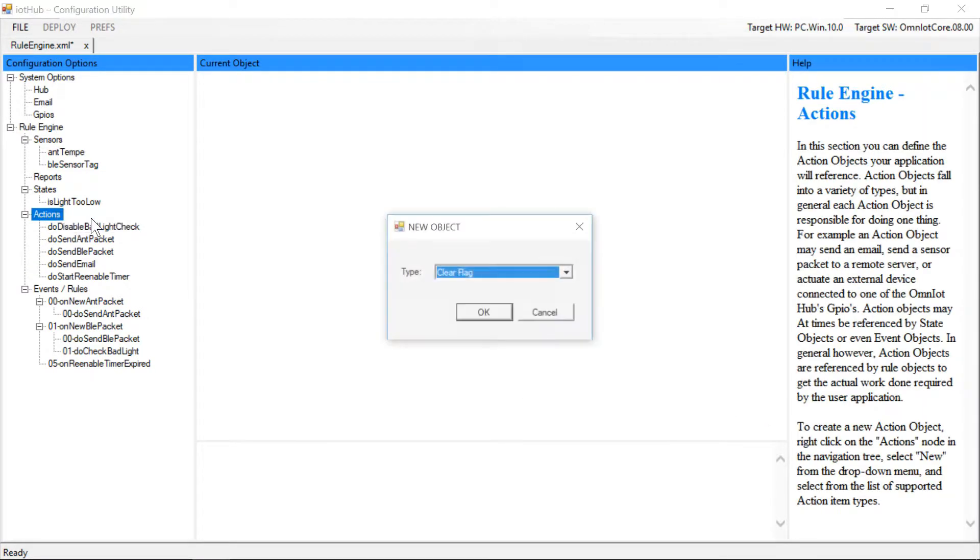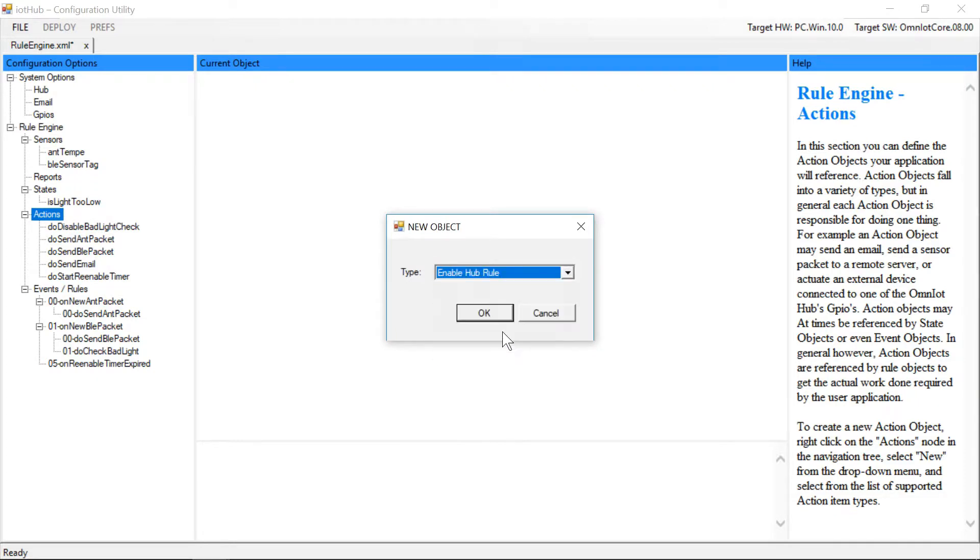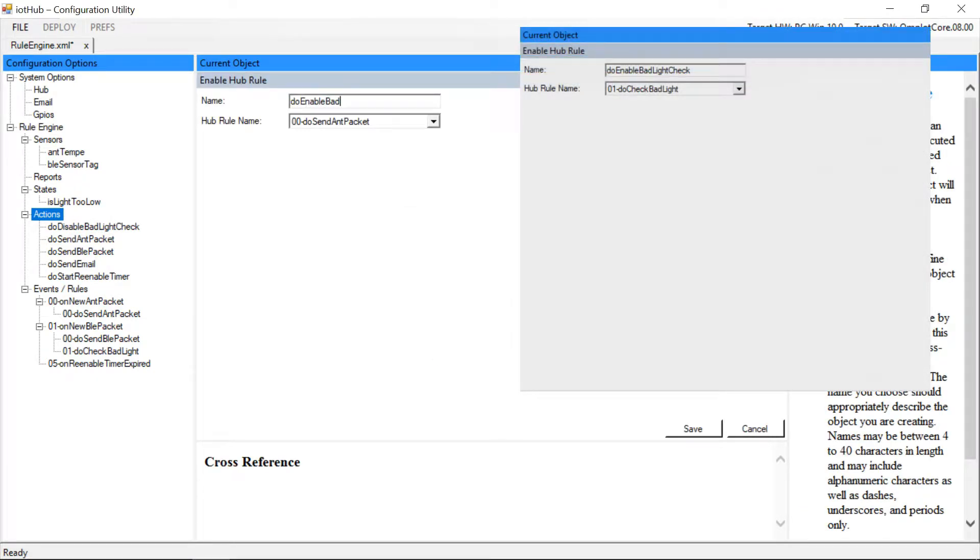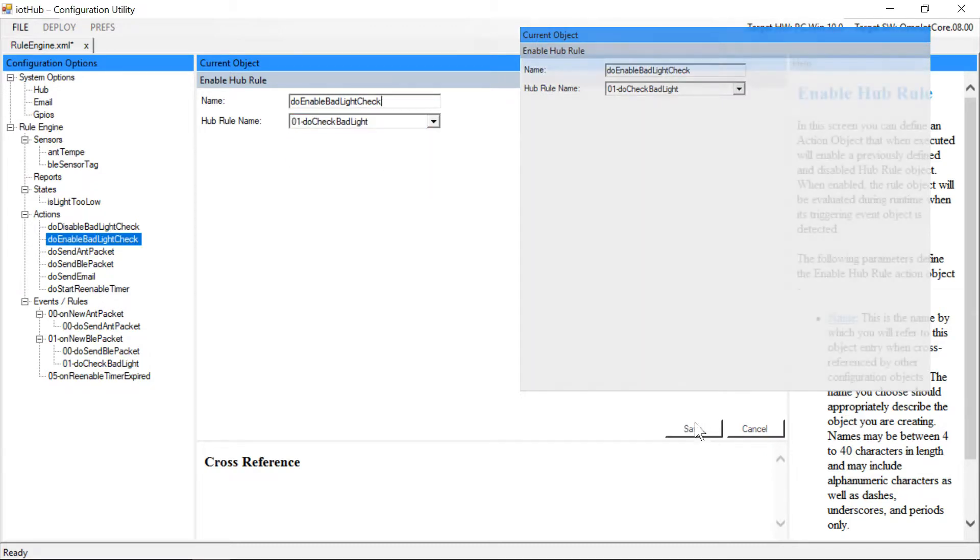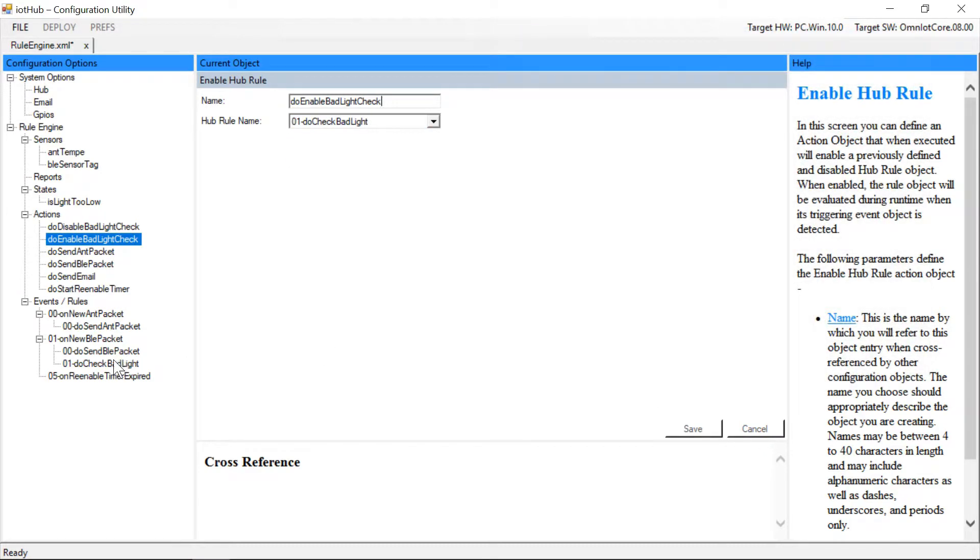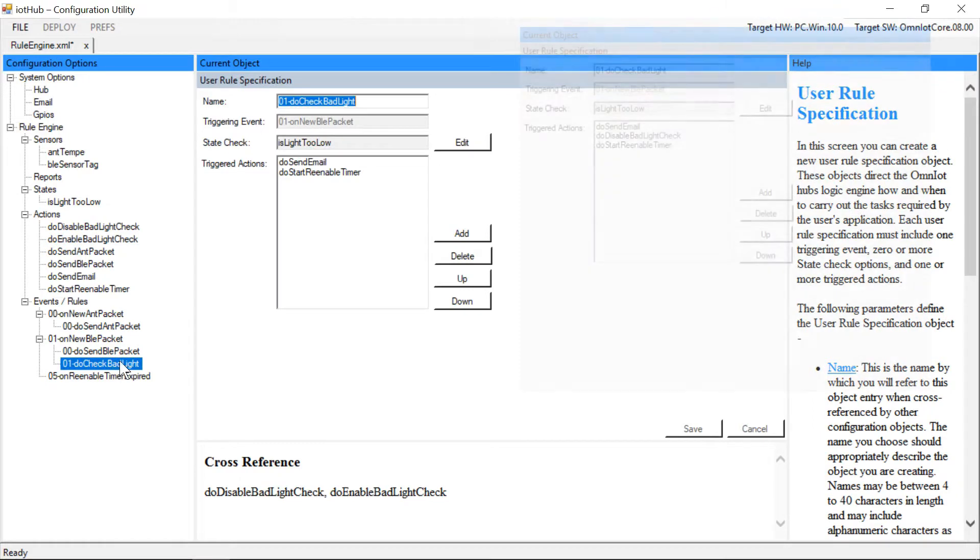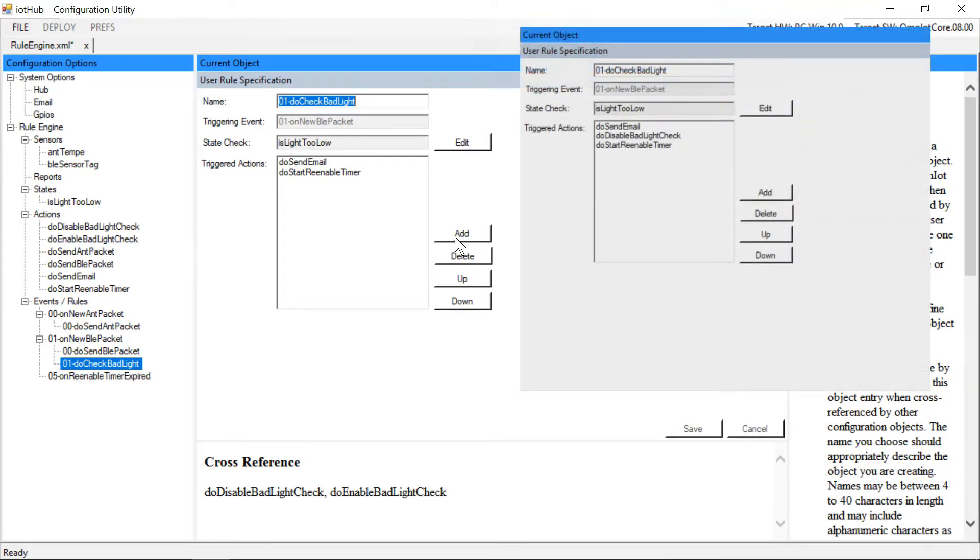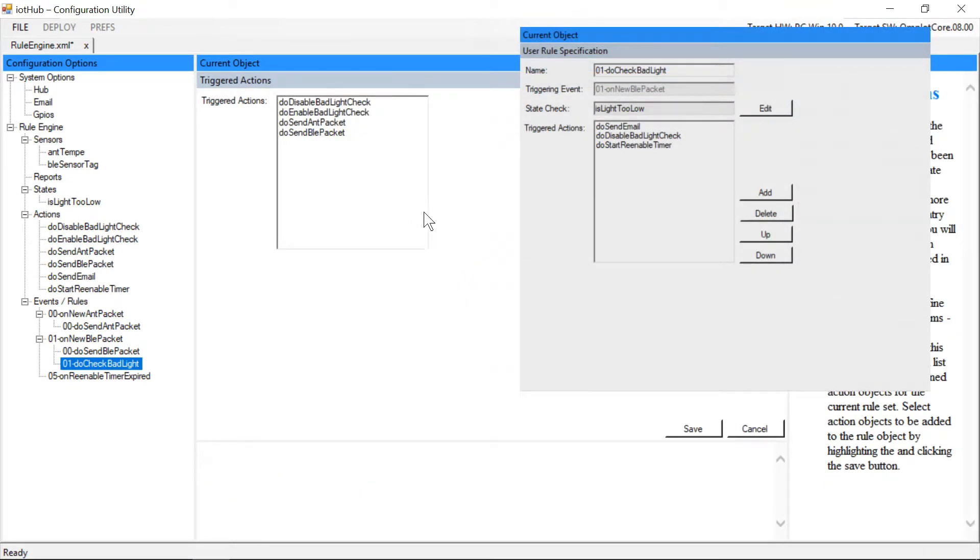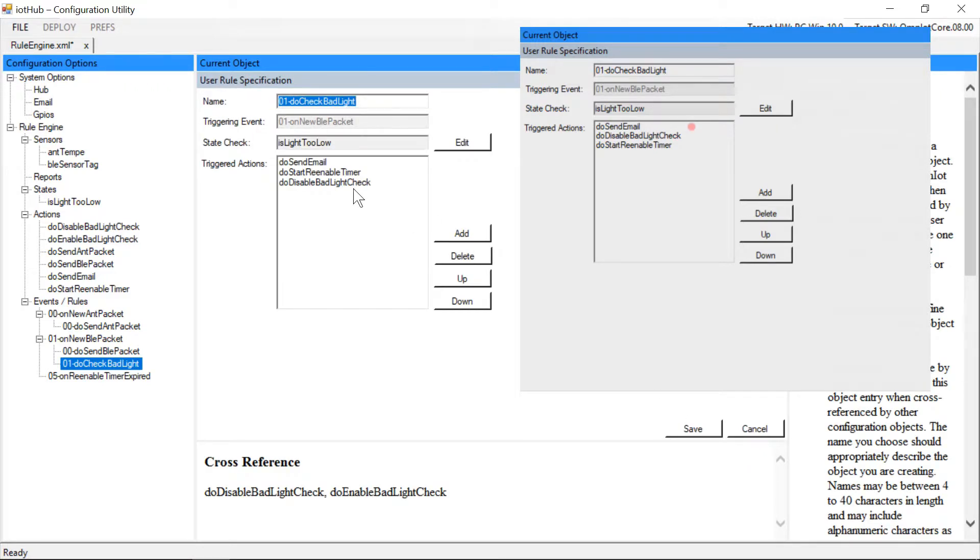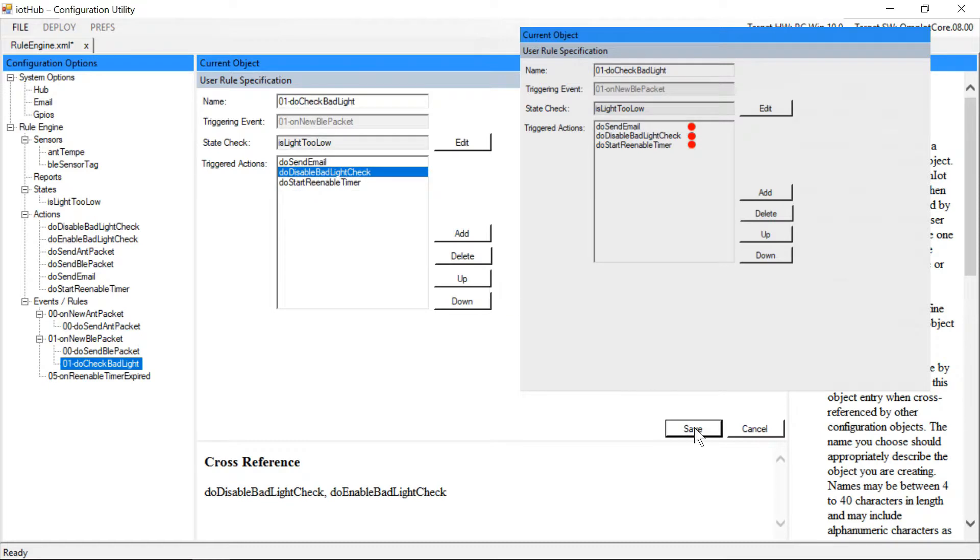So we'll create one last action we'll use to re-enable the rule after the 15 minute timer has expired. Now we'll return to the threshold check rule and add the action object so that when fully executed, the rule will disable itself. Now the complete action list will send our email, disable further checking, and start a timer to re-enable checking.